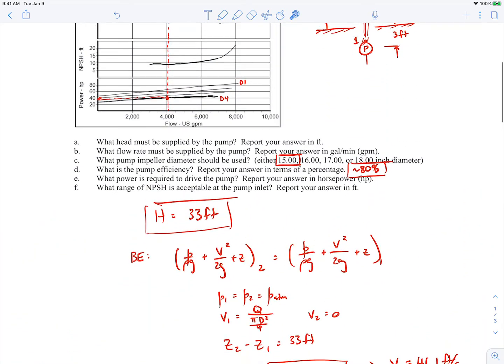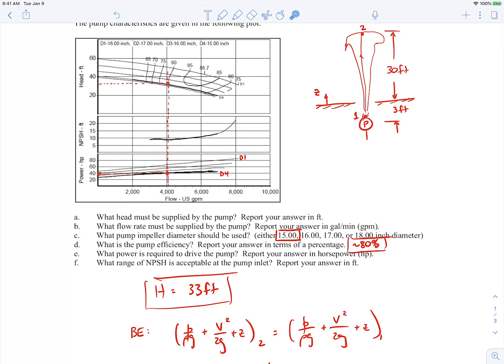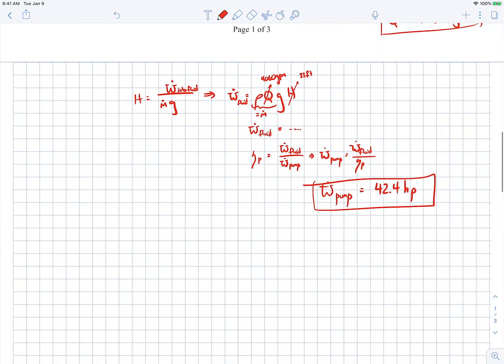Now the last part of the problem is to find what range of NPSH is acceptable at the pump inlet. So to do that, again we come to the plot and we'll go to the NPSH curve. This curve is actually the NPSH R, it's the net positive suction head required by this pump. So we see for our flow rate, looks like our NPSH R is about nine feet. So what we need is our NPSH A to be greater than or equal to the NPSH R, and then NPSH R, we just said, was about nine feet.